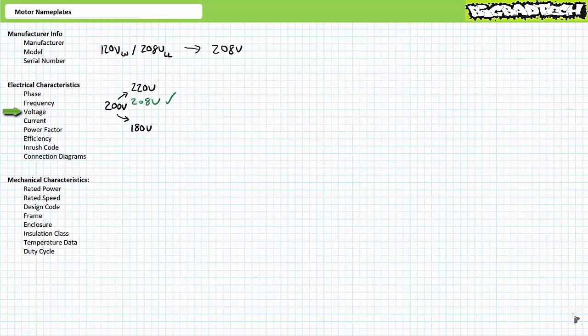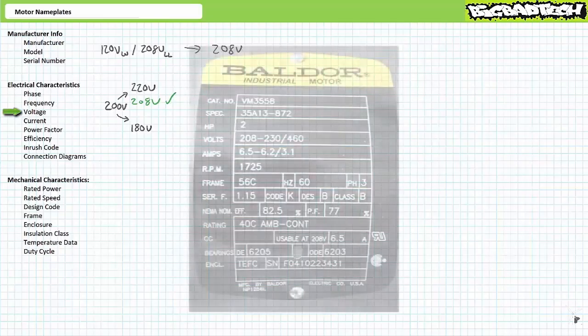This motor would therefore be suitable for a light industrial three-phase AC system characterized by 120-volt line-to-neutral and 208 volts line-to-line. The slightly lower nameplate voltage value of 200 volts ensures the motor has enough punch when it's hooked up to the higher nominal system voltage of 208 volts.